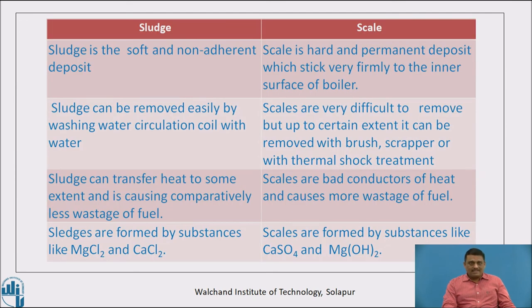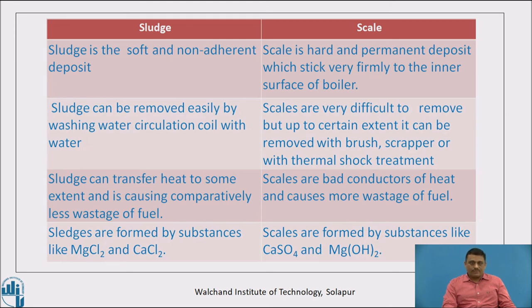In summary: sludge is a soft, non-adherent deposit, while scale is a hard permanent deposit which sticks firmly to the inner surface of the boiler. Sludge can be removed easily by washing the water circulation coil with water. Scales are very difficult to remove but can be treated with brush, scrapper or thermal shock. Sludge can transfer heat to some extent and causes comparatively less fuel wastage, whereas scales are bad conductors of heat and cause more wastage of fuel. Sludges are formed by substances like magnesium chloride and calcium chloride.